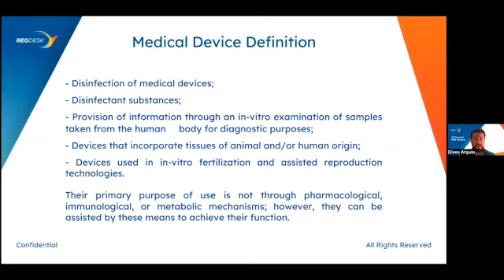So what is the process of obtaining the health registration according to this regulation in Mexico? First of all, you have to determine if your medical device requires a registration, because it may be the case that your product doesn't apply for this kind of authorization, since these products are not classified as medical supplies. But if your product applies for this registration, you have to identify the category of use of your medical device, which can be in some of these 7 categories: the medical equipment, prostheses, orthoses, any other functional aids, diagnostic reagents, supplies for dental use, surgical and curative materials, hygiene products, and now accepted, the software as a medical device as a standalone device. So these are the 7 categories we are going to review.